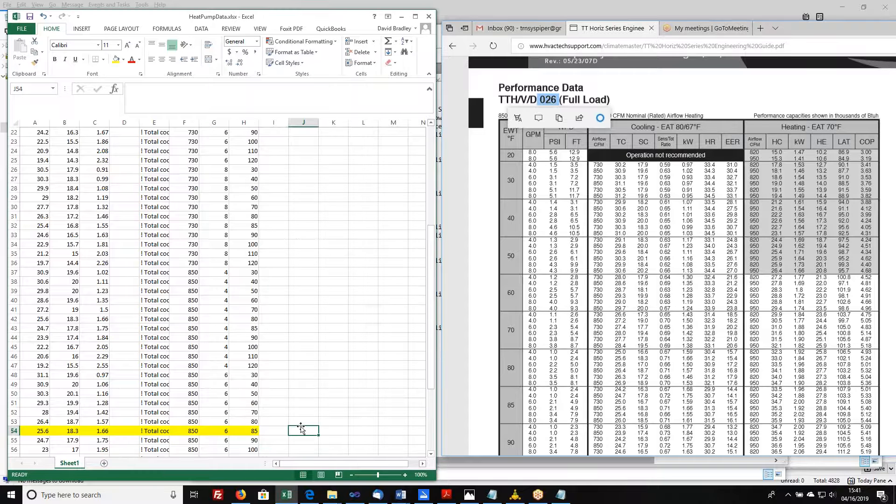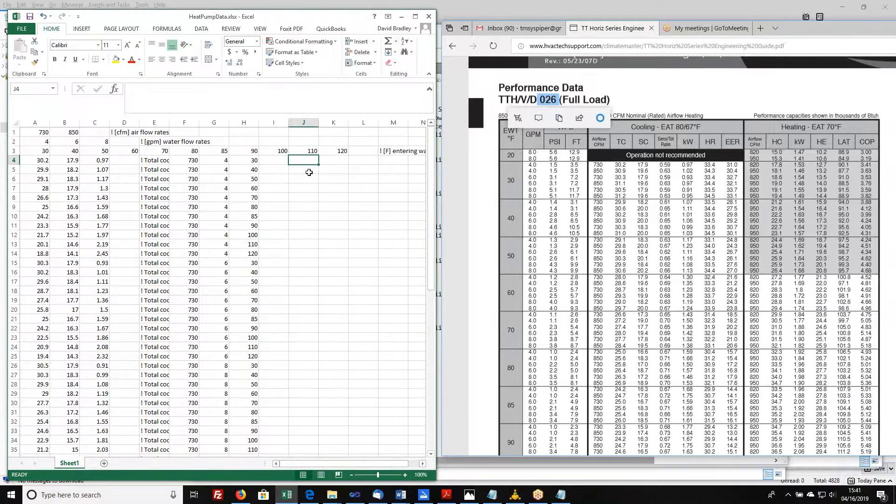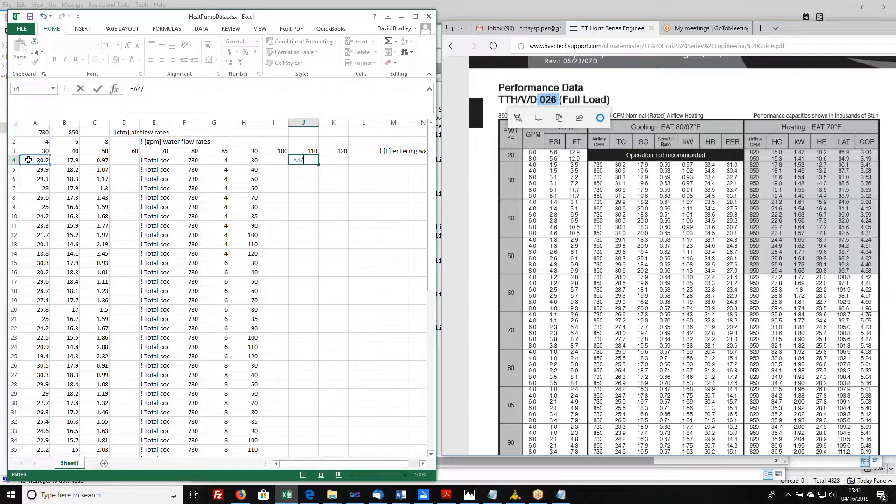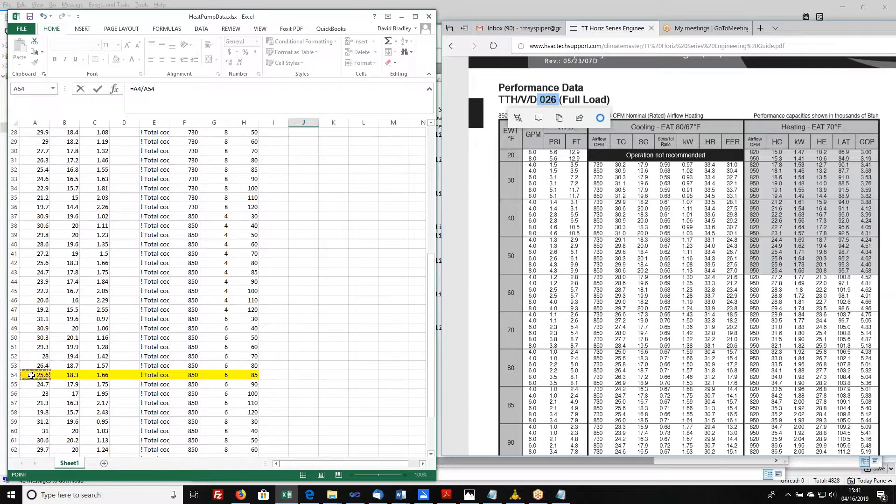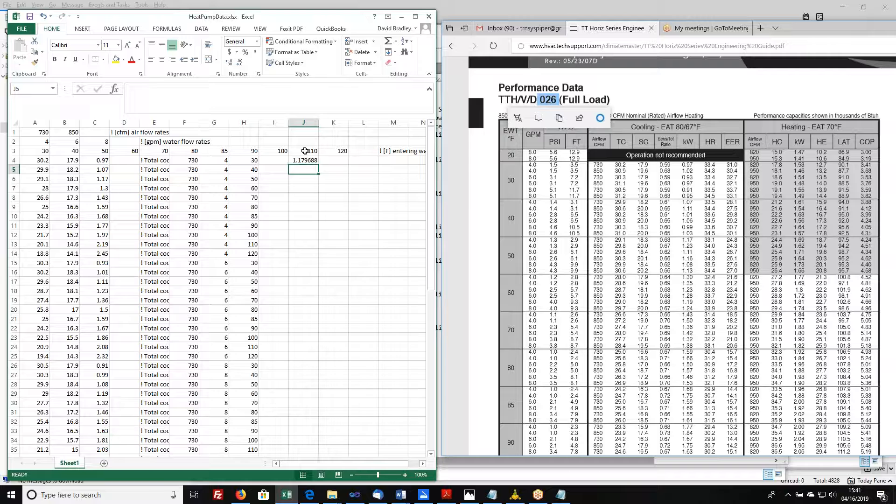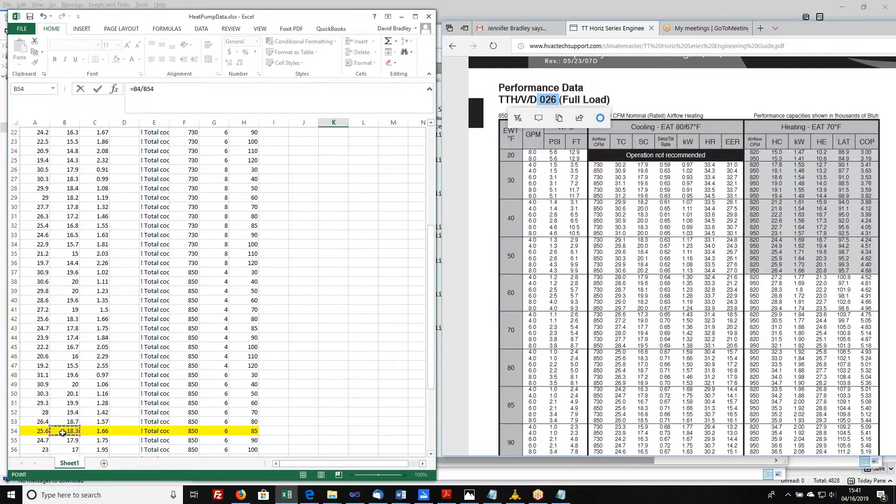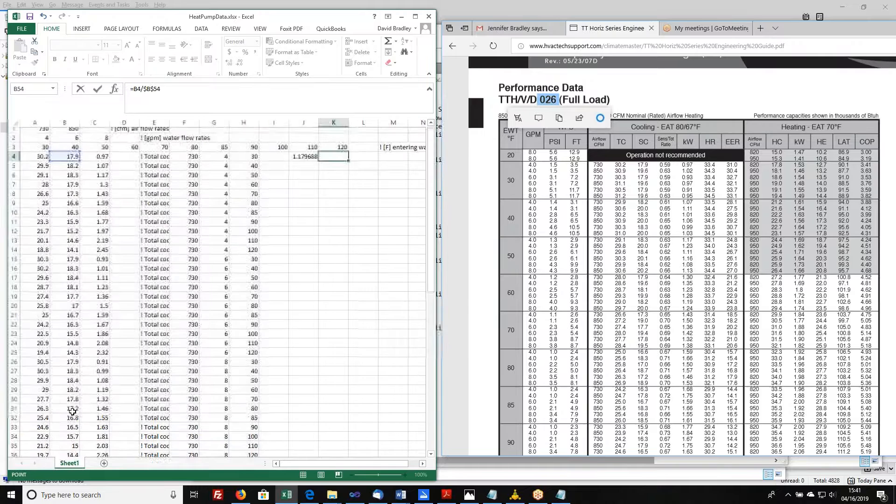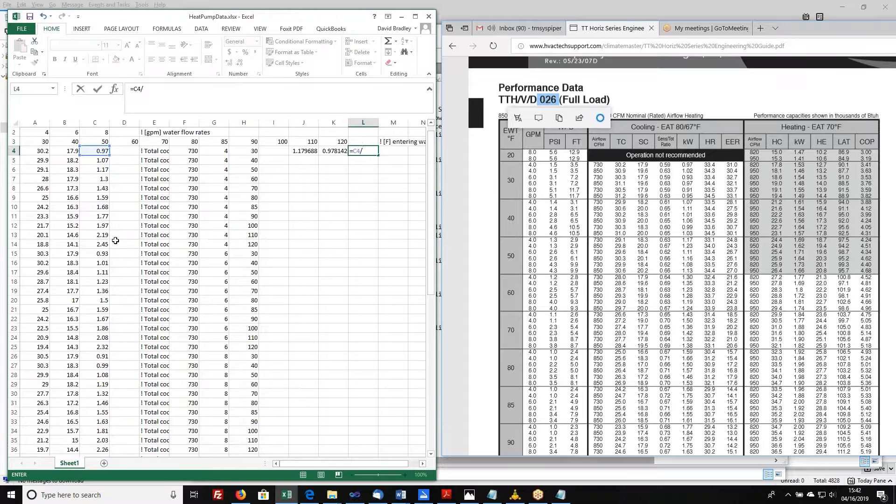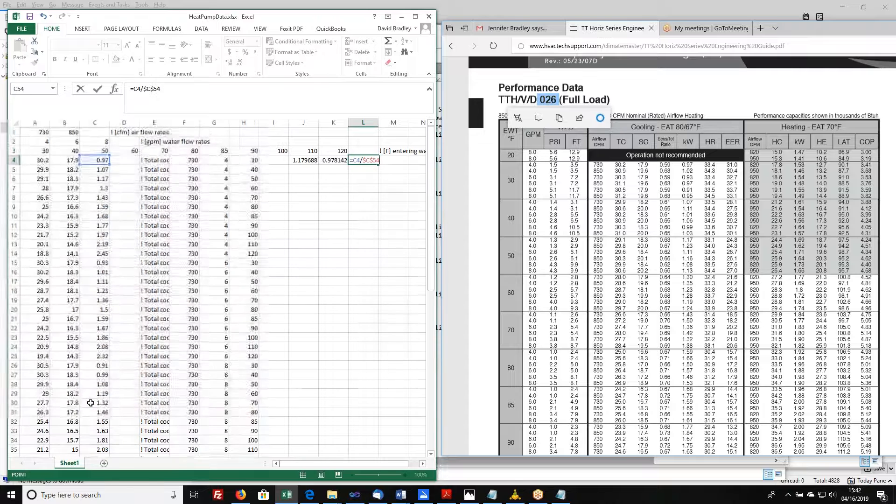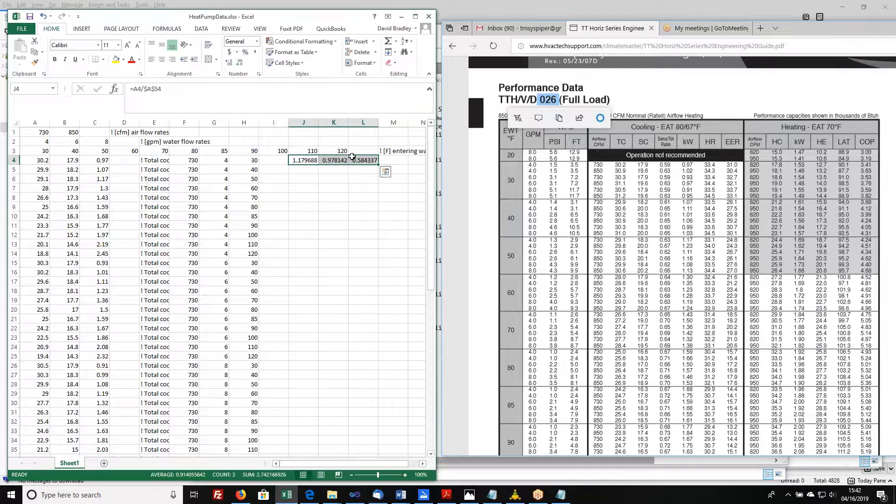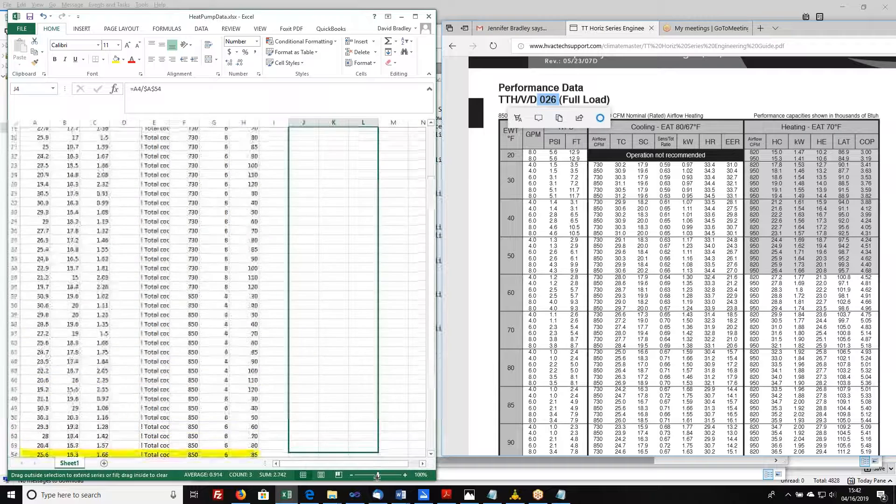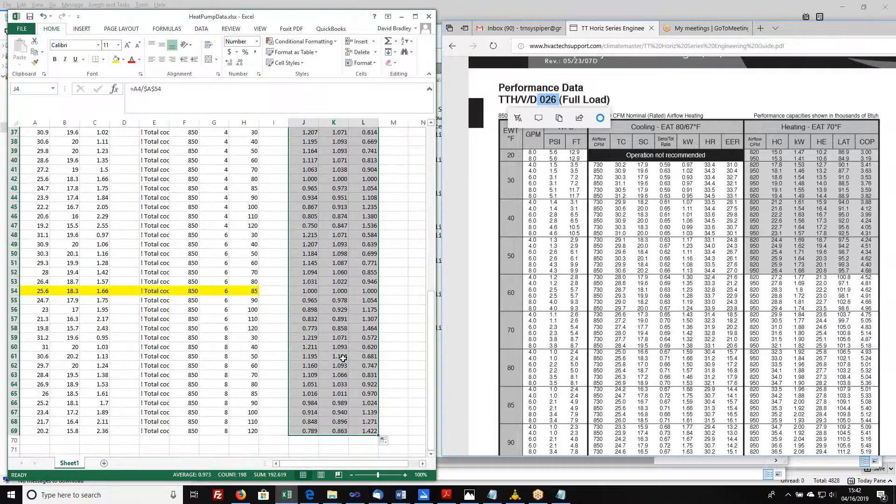So now what we're going to do is calculate the normalized values of all these things. So this value is going to be equal to this value divided by the corresponding value at the rated condition. There's my equation for that. I'm going to do the same thing for sensible and for power. So this is going to equal the sensible cooling divided by the sensible cooling at the rated condition. And this is going to be the power consumption divided by the power consumption at the rated condition. Now perhaps you see why it was that I didn't really worry too much about the fact that these are not the units that I want to deal with. So I'm going to take these and pull this whole thing down. And here I've got the data file.